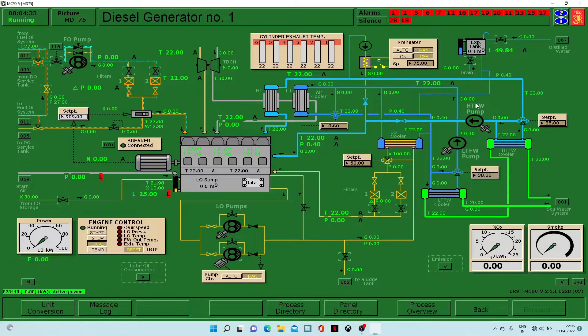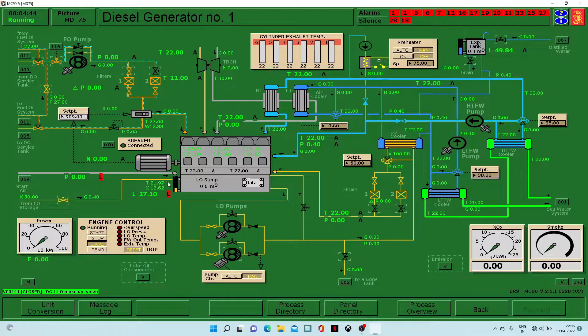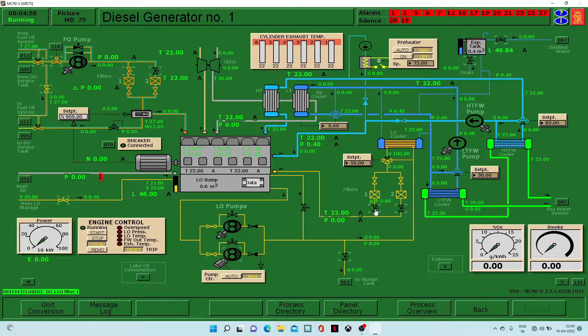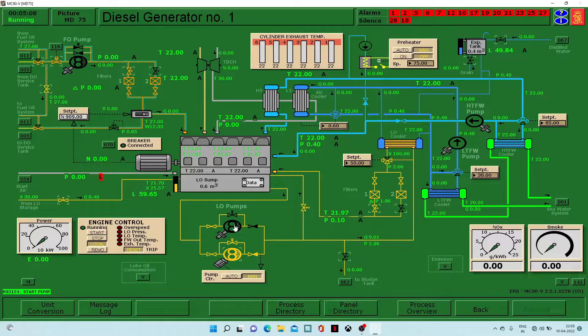We'll click on diesel generator one and this screen will appear. First, we will turn on the fuel oil supply — these two valves. We will increase the level of lube oil in the lube oil sump; it should be nearly above 70 to 75. Then we will close this valve. Meanwhile we can turn on the lube oil pump. First we have to open the valve going to the filters, and after that it will go directly to the main engine.